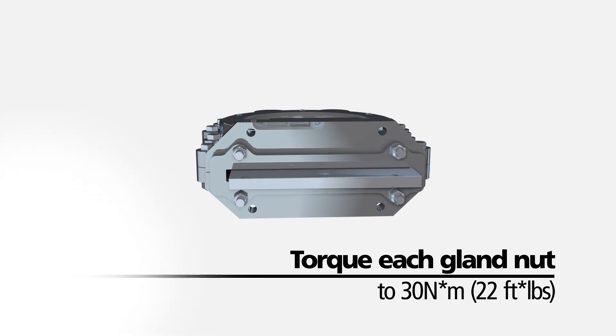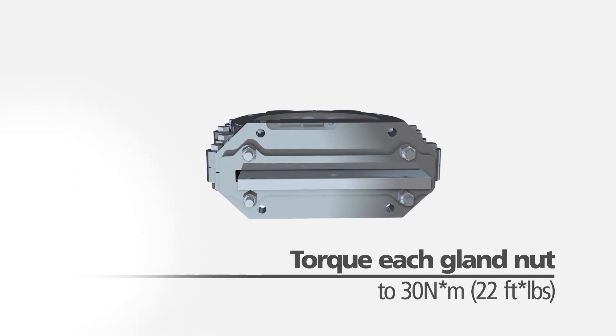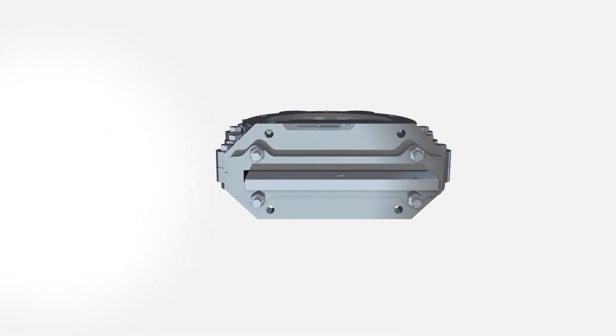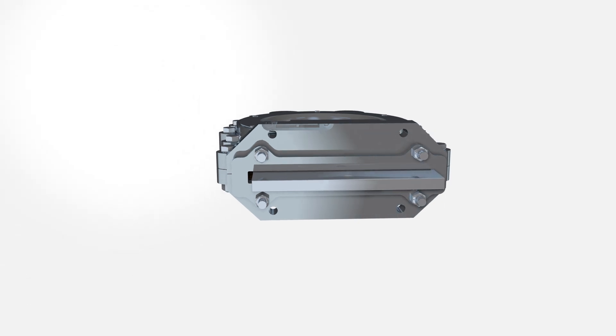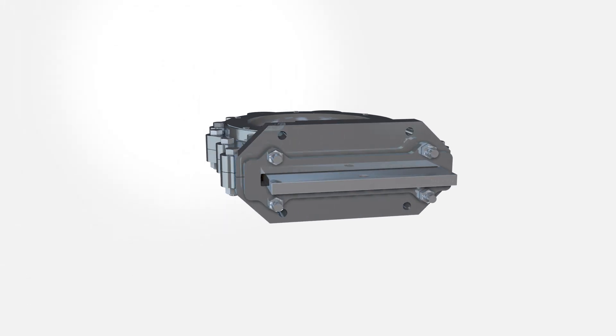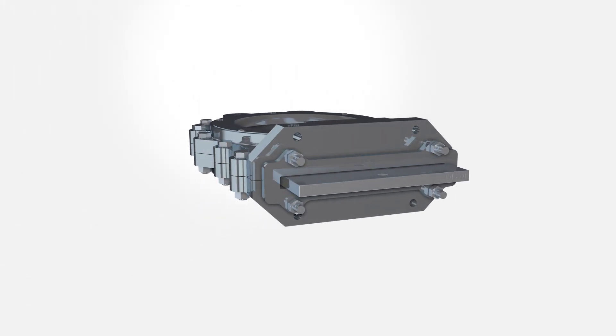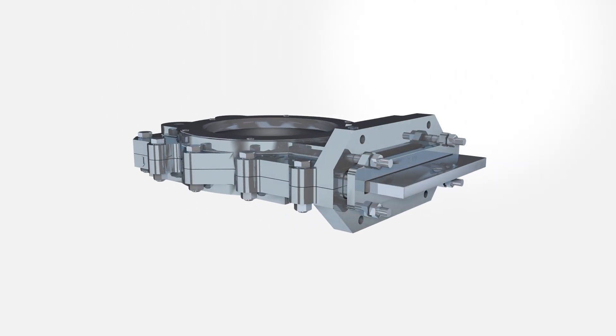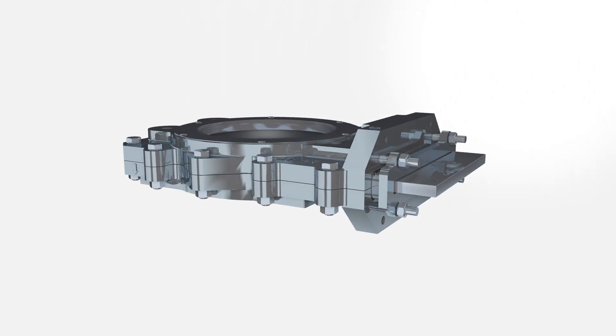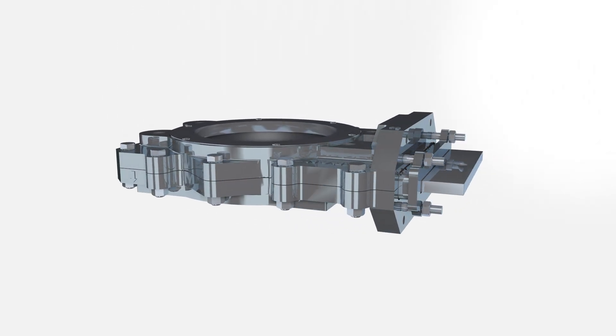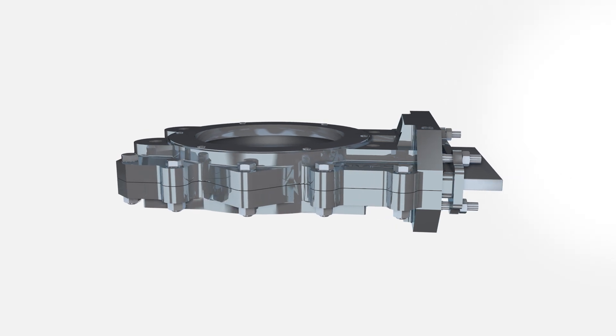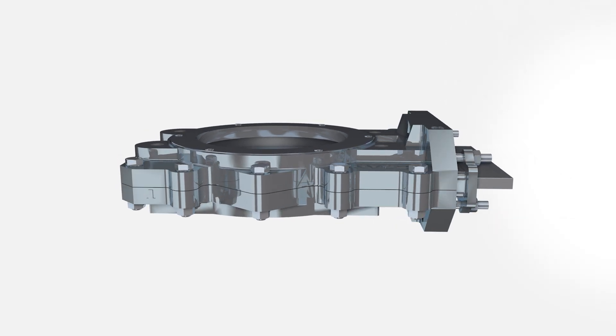Do not over-tighten the packing nuts. When packed too tightly, the movement of the slide gate can be restricted. If the packing leaks at startup or soon after, tighten the packing gland nuts with an open-ended wrench until the leak stops. In most cases, the packing gland can be tightened with the valve installed.